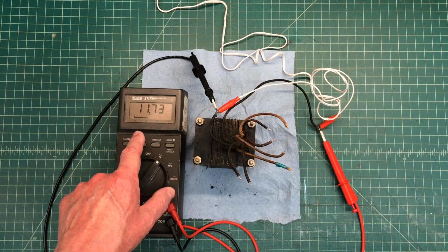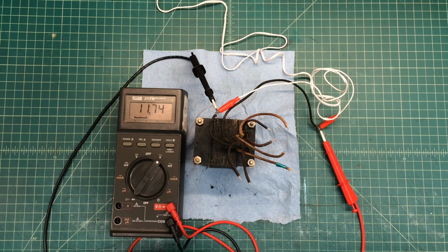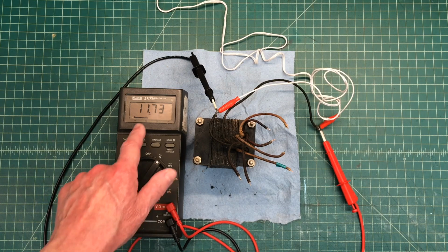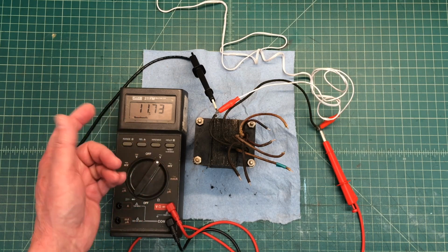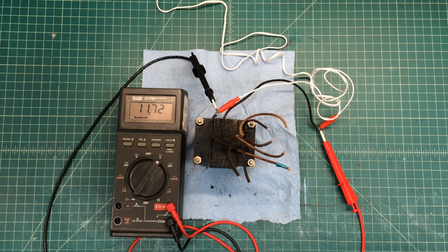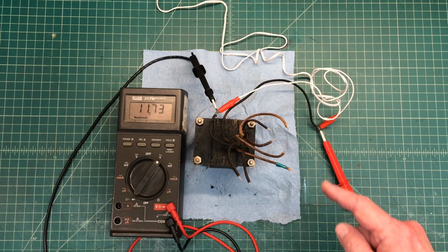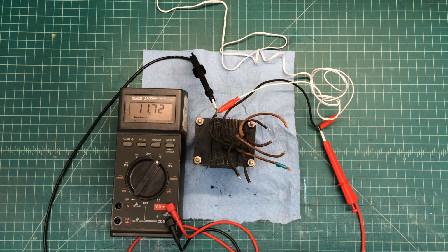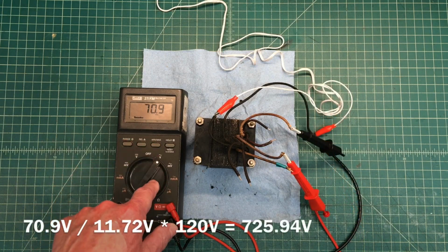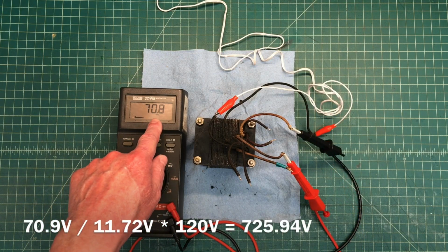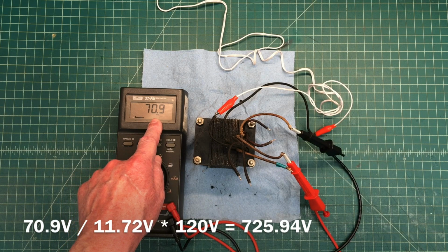Let's extrapolate the AC voltages off of the transformer. I'm inserting about 11.7 volts across the primary. Let's measure the output voltages, and I'll show the math for what the output voltages of the power transformer would be with no load. You can see the high voltage winding is right at 70.9.